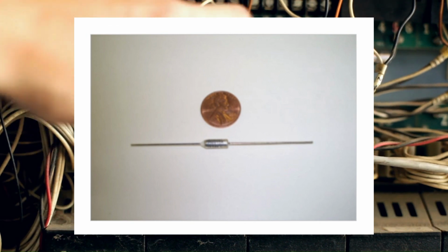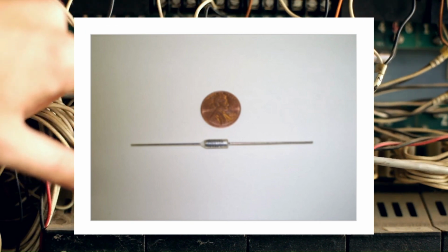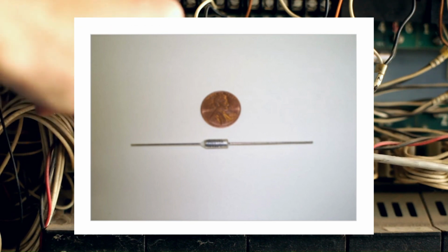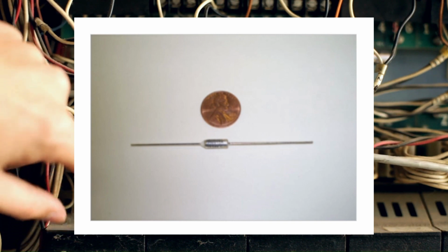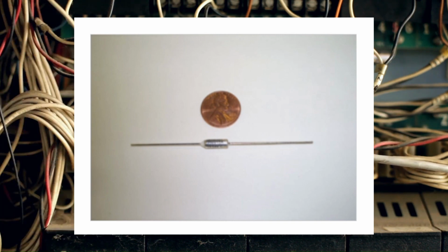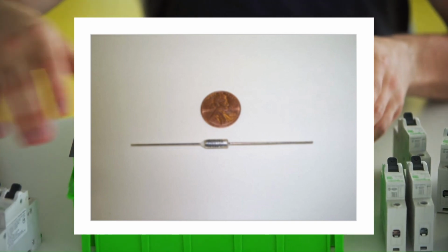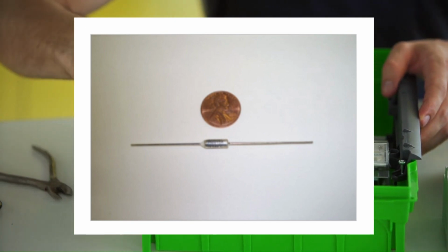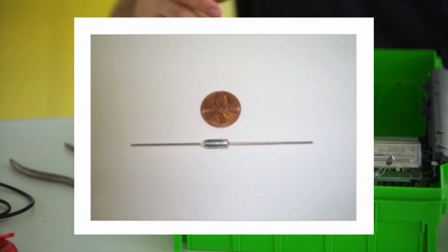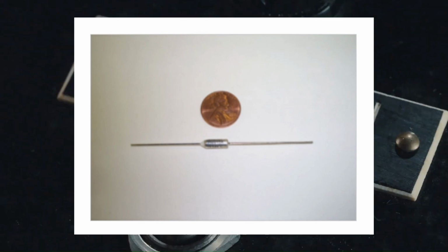Manufacturer information is printed on the silver cylinder. Temperature and amperage ratings could be among the details. The cylinder-shaped object features a tapering end and a square end. Depending on the color of the material used to make it, the taper may be either black or red. To check if a link is open, measure its resistance. It should show a resistance of 0 ohms.